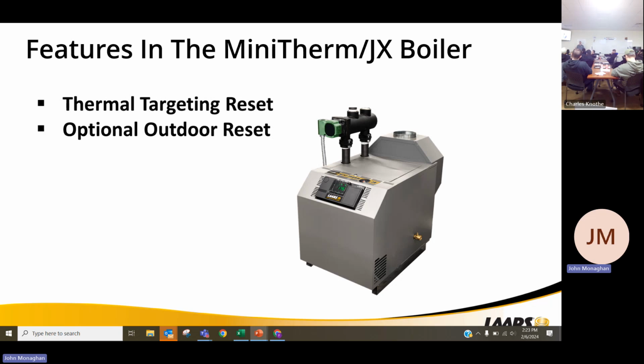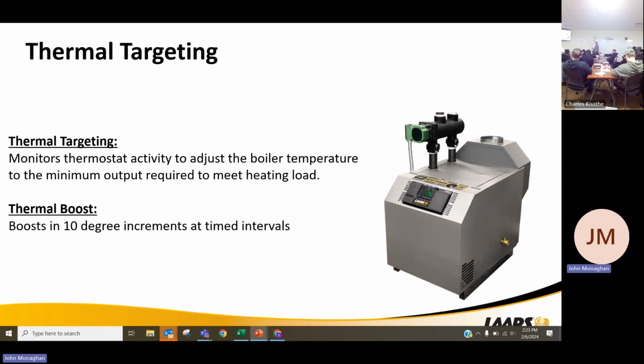You can thank the Department of Energy and the 2012, 2013 initiatives for this. The other portion is going to be your optional outdoor reset. And the outdoor reset is going to work just as it would on the wall hung high efficiency products. It's going to take the outdoor air temperature and adjust the new set point for the boiler. Is thermal targeting optional, or can you turn it off? You can't turn it off. It comes on because of the DOE.